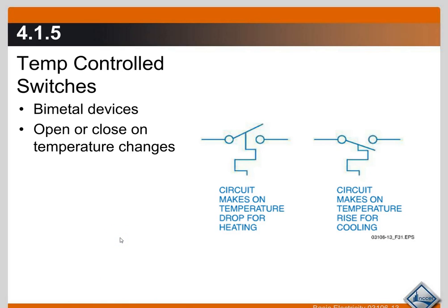That is basically how all temperature-controlled switches work — when the temperature drops, it makes or closes the circuit. The opposite is making on temperature rise for cooling. If your thermostat is set at 72°F in cooling mode, as the temperature in the house rises to that point, the switch closes and turns on your air conditioner. This symbol right here indicates a temperature-controlled switch.